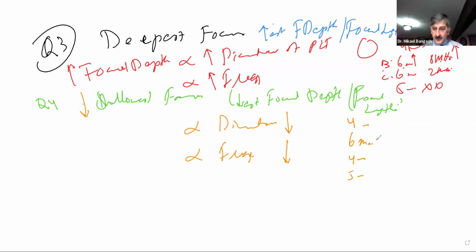So in this case, this one here and this one here are out of the race because both 5 and 6 are greater than 4 millimeters. So we just have A and C. Clear? Okay. Now we just have to look for the lowest frequency as well. Which one of these two here has the lowest frequency?